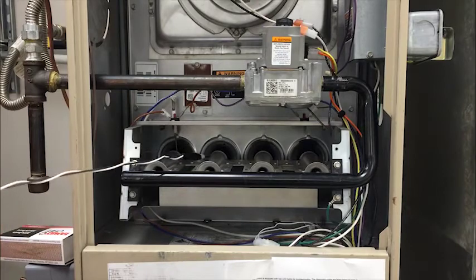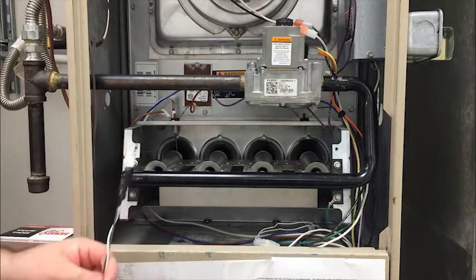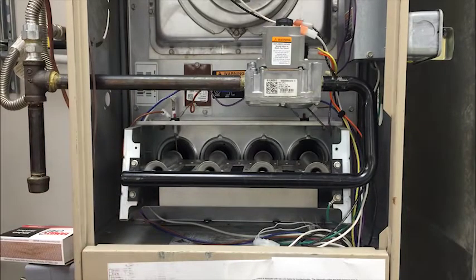Now we can go ahead and utilize one of our other test methods, like an inspection camera, inspection mirror, or disassembling the furnace and looking at the heat exchanger itself to verify it. But this quick and easy test will allow you to see if you have a damaged or breached heat exchanger in a very short period of time. Thank you.